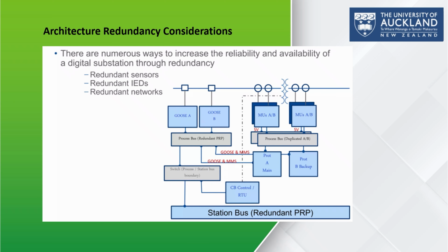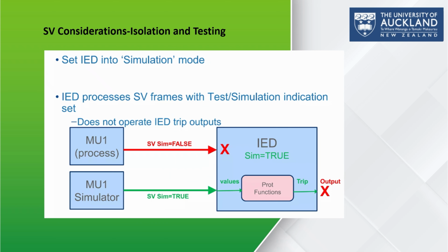So, sample value considerations, isolation, and testing. This diagram explains how an intelligent device behaves when it is placed in simulation mode. In this mode, the relay is prepared to accept only the simulation sample values for testing purposes. This prevents the device from reacting to a real process measurement while engineers perform functional or system testing.